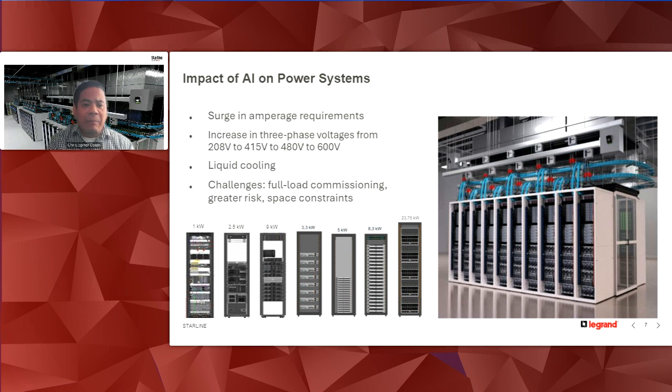Today, we're very commonly seeing 23, 24 kilowatts of rack power, but we're also seeing the roadmap of what some of our customers are doing as well, right? We're seeing requests that are coming in the next year for 50 kilowatts to 100 kilowatt racks. Beyond that, we're even asked for 150 kilowatt racks. And in the long term, it's going to be even larger than that. So again, reiterating the fact that there's no stopping this increasing of power demand within the AI space.